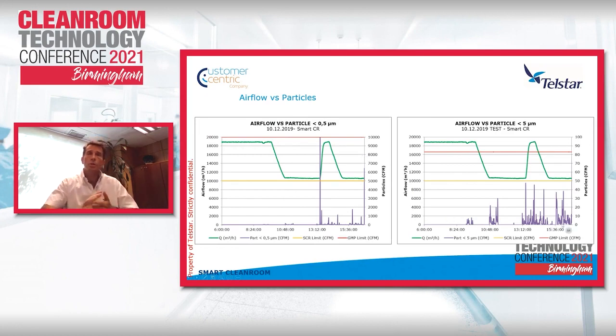We are now going to show some other diagrams of tests we made. What you can see here, the red line is the GMP limit, in cubic feet per minute. Then the yellow one is the smart Cleanroom limit, the one that we put as a reaction criteria for particles. The green line is the flow rate that we were giving to the system. And the purple one is the particle counting, particles of 0.5 microns.